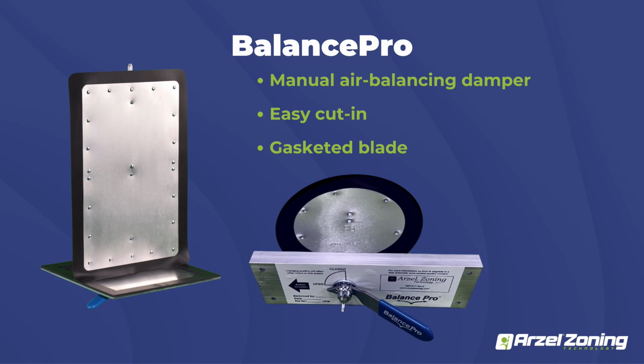And the last damper that we offer, which I had no idea that Arzel offered until I actually started here, is our BalancePro damper. I'm sure you guys are all familiar with balancing dampers and how hard they are to install after the fact when the ductwork is done. You got to pull the ductwork apart, you got to drill your holes, you got to insert the blade itself. The nice thing with the BalancePro, for one, it's got a gasketed seal, so it's going to seal off 100% of that airflow if you need it to.